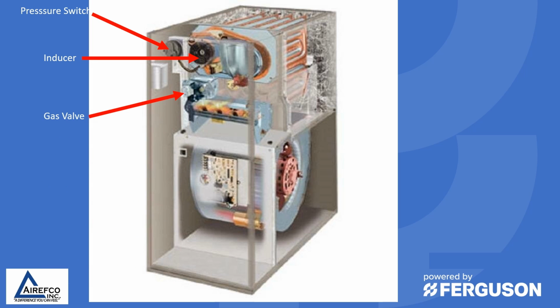The gas valve is another item that is most often misdiagnosed. I had a guy the other day who was condemning the gas valve and was ready to go get one and change it out. And I asked him to check the voltage coming from the control board to the gas valve. And he found that when the gas valve was dropping out, the voltage from the control board was dropping out. So it was not a gas valve issue, it was a control board issue. So properly diagnosing these components is very important to getting the job done correctly.